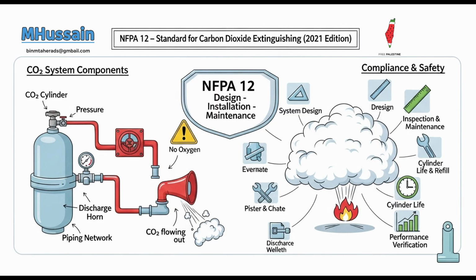What about the alarms on ships? Marine alarms also have a critical difference from land-based systems. The audible pre-discharge alarms and time delays, which must be a minimum of 20 seconds, must depend only on CO2 pressure as their power source, not external electricity. Alarms powered by the CO2 pressure itself. Yes. This is a vital design choice, ensuring they function even if the vessel experiences a complete loss of electrical power during an emergency, maintaining a critical life safety function when all else might fail. Power goes out, alarms still work.